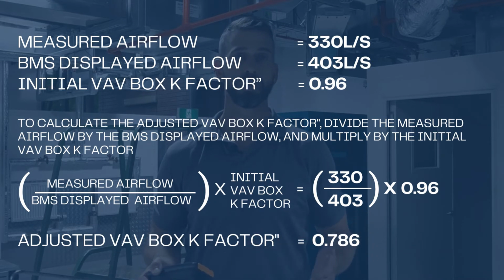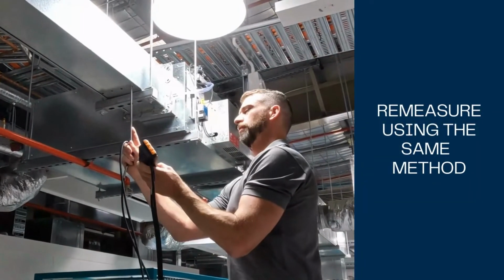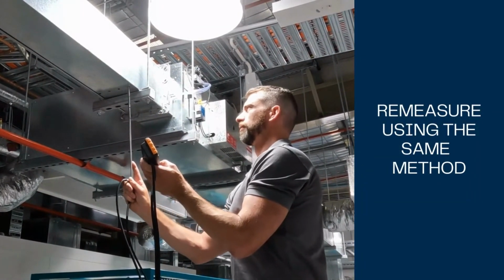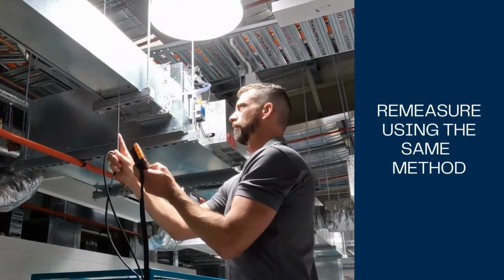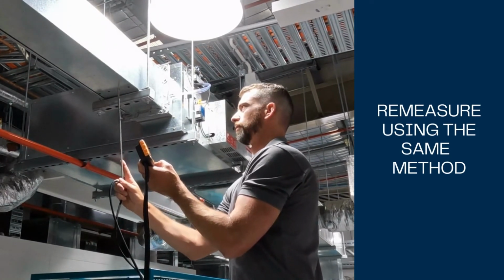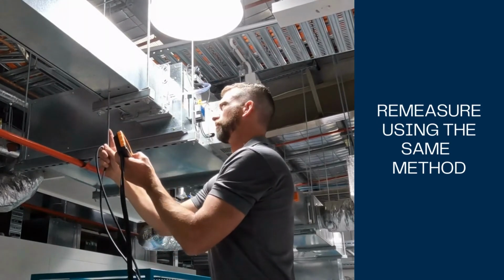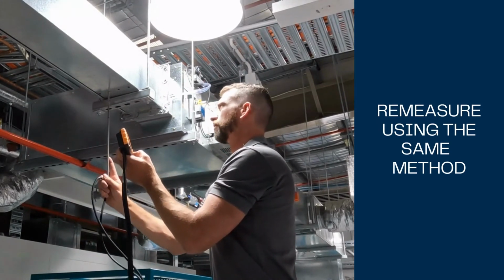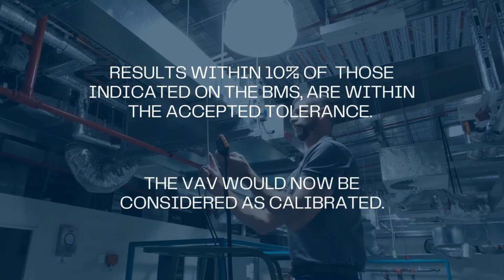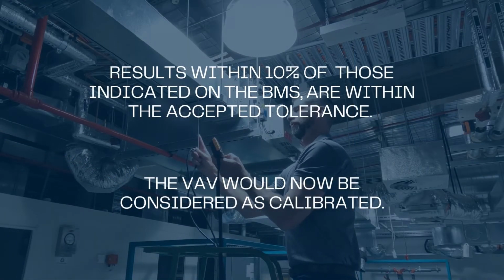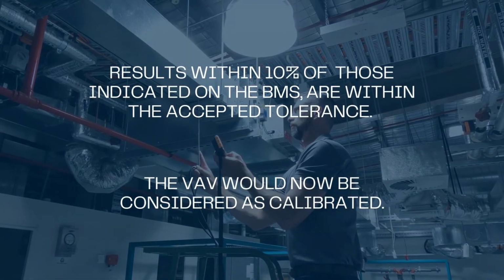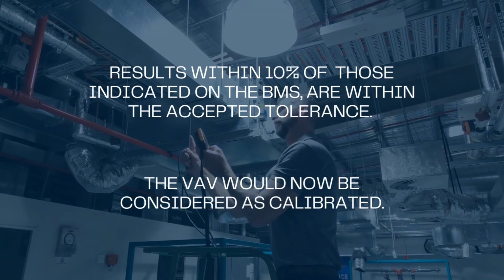Now, at this point, it's really important that we retest the airflow to see that the new K factor is held and that it is accurate. So let's go and measure it. We remeasured the airflow at 408 litres a second, with the BMS indicating 402. This is well within the typical 10% tolerance range. As such, we'd regard this as calibrated.